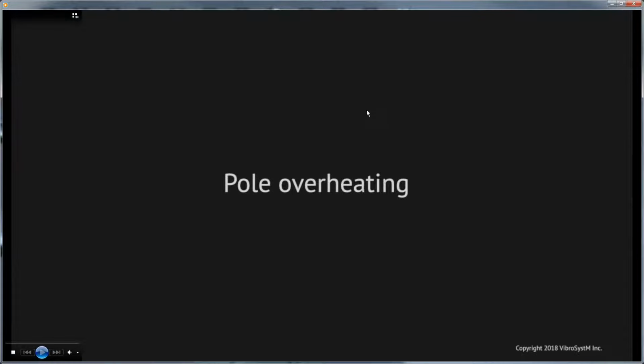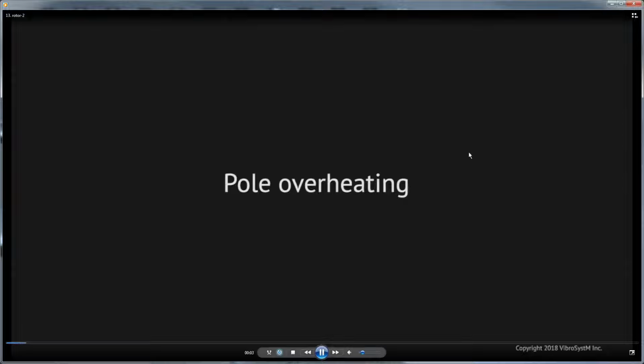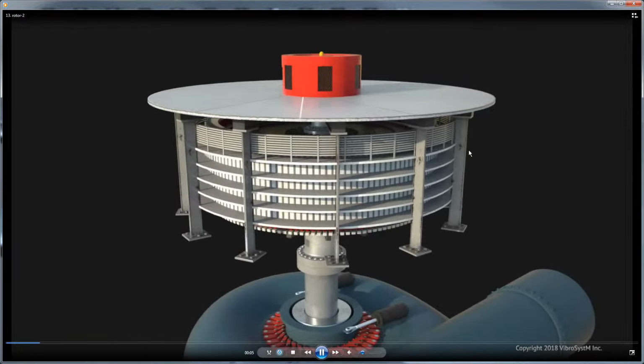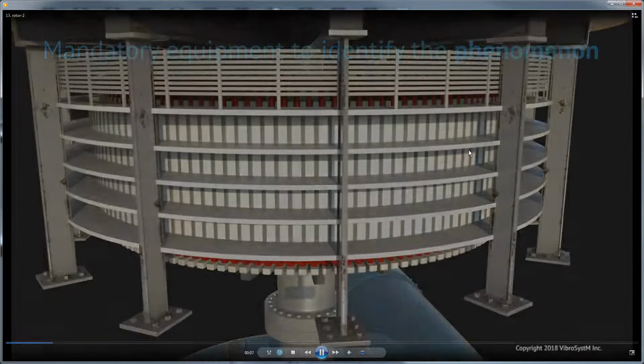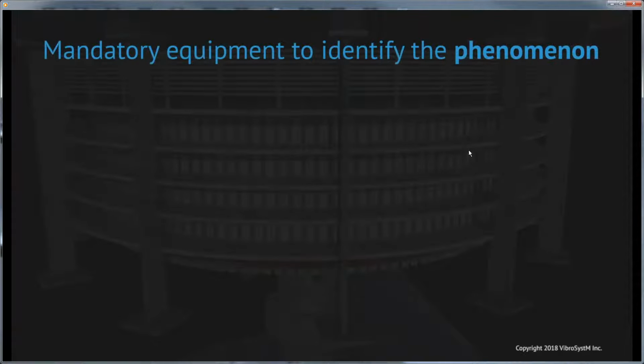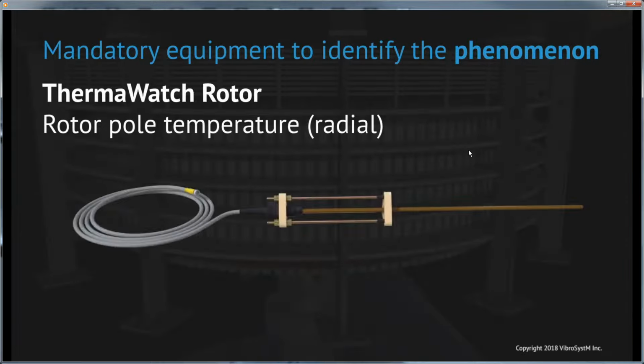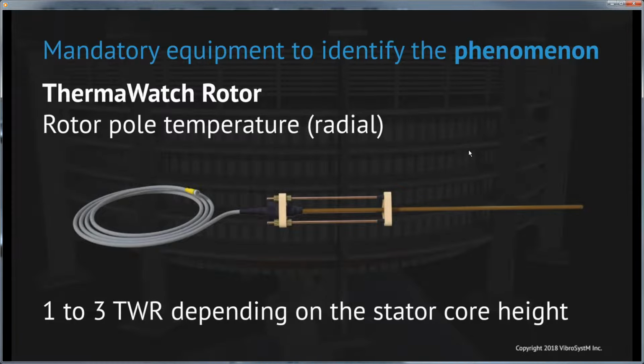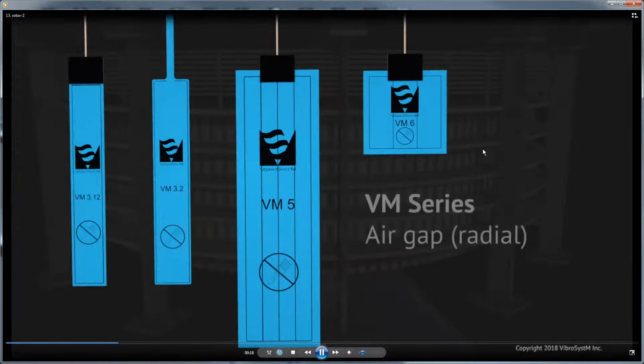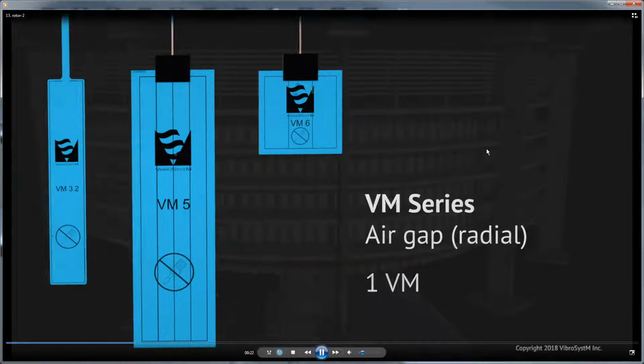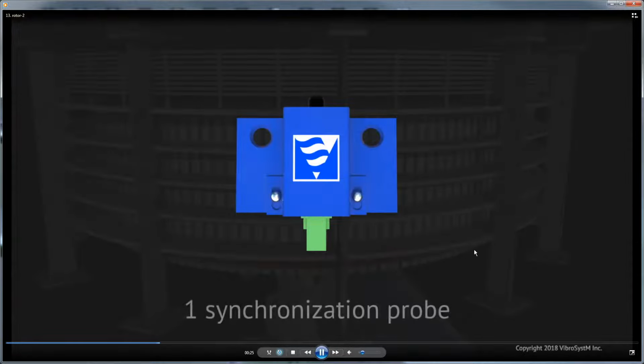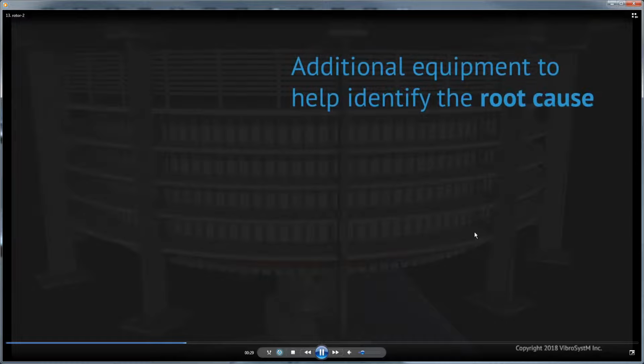Okay, so we have this last presentation for pole overheating. Okay, so to be able to monitor that, you need, of course, at least one ThermaWatch rotor. We recommend 3, but you need at least one. You need air gap to give you a reference to which poles are which. So it's nice to detect a pole that's overheating, but which one is it? So with the synchronization probe and the air gap sensors, you're able to identify.